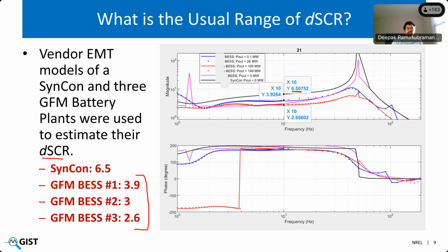Yeah, and adding on to that fast timescales perspective, it's a very crude way of drawing a mapping between the frequency domain and the time domain. Saying it outright, it's very crude, right? So it shouldn't be dissected to nth detail, but a very crude approximation is that a 4 hertz frequency perturbation will relate to a quarter cycle duration of roughly 60 milliseconds or 50 milliseconds. So it's roughly looking at the speed with which a voltage step change or a frequency step change would occur, or the ramp at which that would occur, and then the kind of response that we want for that kind of event. That plays a role in determining the frequency range. And as Shahil mentioned, it can be changed around depending upon network to network.